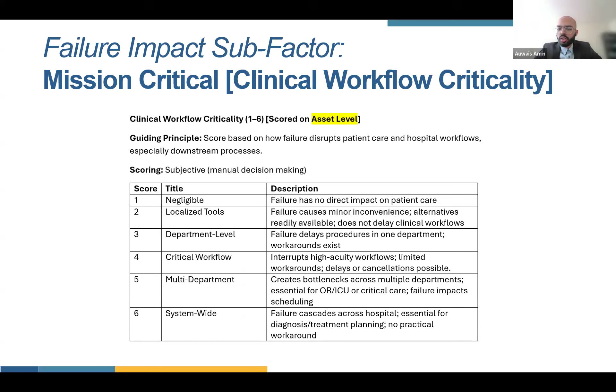Similarly, for the likelihood sub-factors, the failure rate was another thing that CMMS in TOH is tracking, where it tracks the average failure rate of a device in a year, using the failure codes, which was adopted in one of the white papers in AAMI. The one that we have implemented is how we track these failure codes, which would then give out the failure rates. Based on that, I came up with a description table. Because in this case we are tracking it on CMMS, I chose to come up with a more granular table here, as this would be an example of, as the maintenance is being done, all the data is being tracked, and the CMMS can then eventually, over the life cycle of a device, analyze what the failure rate had been yearly.